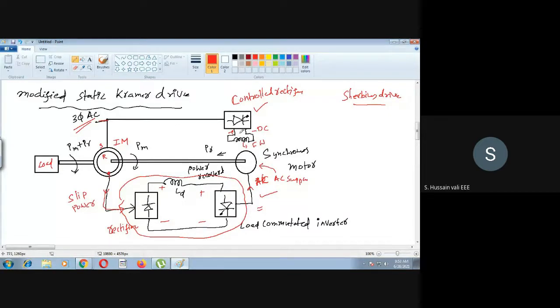Then you will get the DC out of that rectifier. That DC goes to the field winding of the synchronous motor. Whereas the armature gets supply from the load commutated inverter, then you know the working of the synchronous motor - it will generate a torque. So the power here, PR, you can call this power the recovered power.